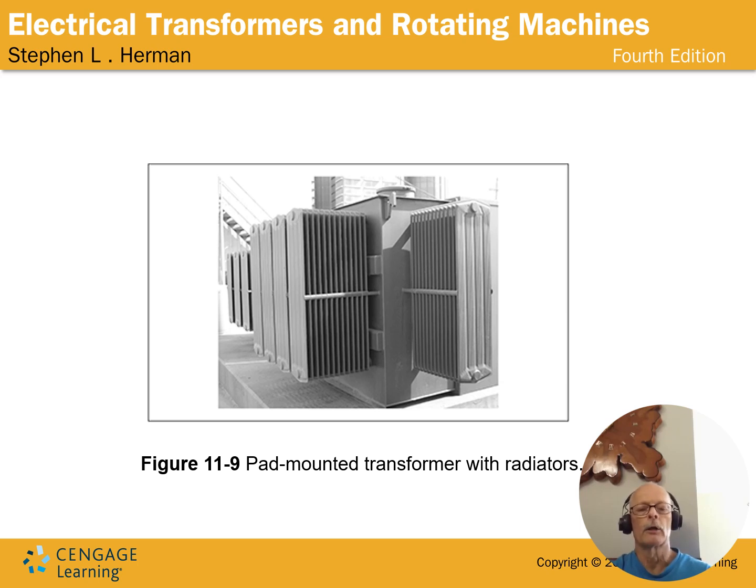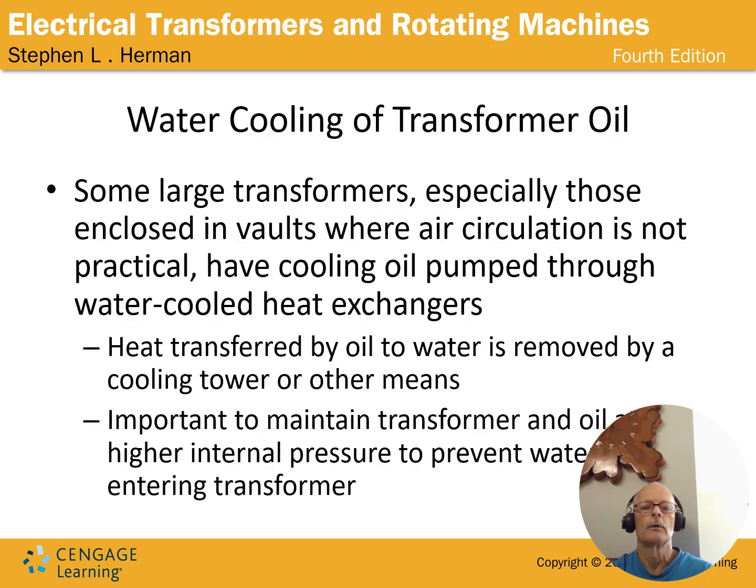And this one's got a lot of cooling on it. A lot of oil going out and down here. One, two, three, four banks there, and a bank on each end, probably four on the back. You know, that's ten banks of cooling fins to keep that transformer cool. And it's worth it because transformers are very expensive. So you spend this extra money to protect your investment.